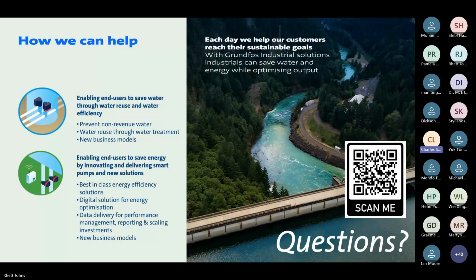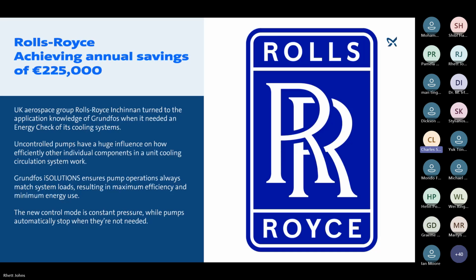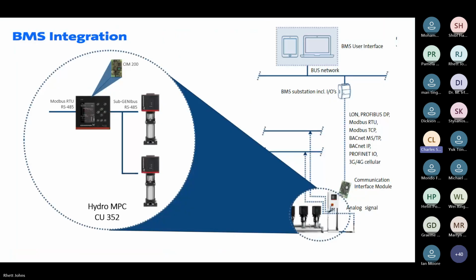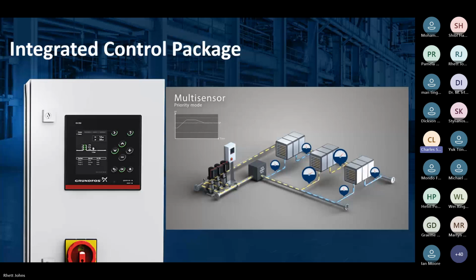And that graphic, I don't know if you can jump back to it, Gret. That's a video graphic that we have of the system where it's automatically updated. That's doing exactly what we're talking about. There you go, that's the one. So this is a system the same as any other system, where it has highs and lows of demand depending, in this case, on the time of the day or night. And as we mentioned, that's one of the beauties of having an intelligent control attached to it: it does it autonomously, as Rhett said, so it can adjust the pressure accordingly. And this is where you make those efficiency savings.